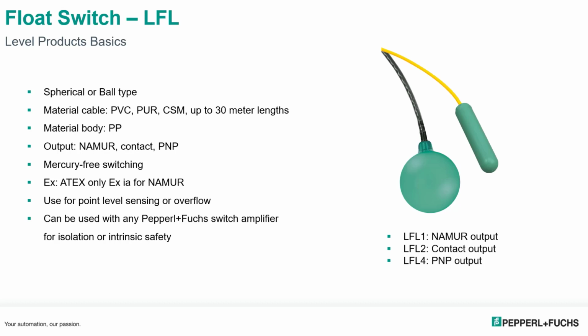The material of the cable can be PVC, PUR, CSM, and up to 30 meter cables, depending on the medium you have. The material body can be polypropylene. We have different types of outputs. We have a NAMUR output for hooking up to an intrinsically safe barrier or for isolation, contact, or PNP 3-wire type outputs. These are all mercury free. There's a ball inside these switches that activates a micro switch.